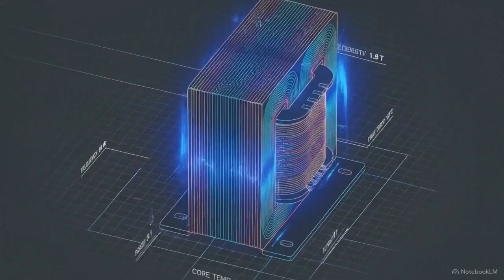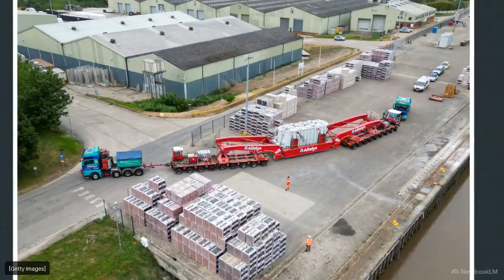Furthermore, large power transformers are bespoke, labor-intensive engineering projects designed to fit the exact voltage parameters of a specific substation. The manufacturing base is experiencing a supercycle demand shock: the grid must absorb the rapid expansion of gigawatt-scale AI data centers at the same time it is interconnecting massive utility-scale renewables. Domestic factories cannot meet this demand, forcing the U.S. to rely on foreign supply chains for roughly 80% of its large power transformers.